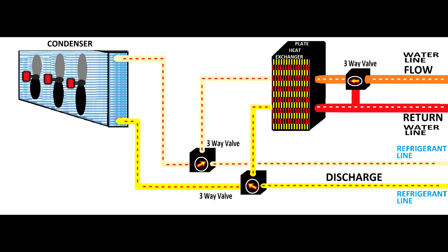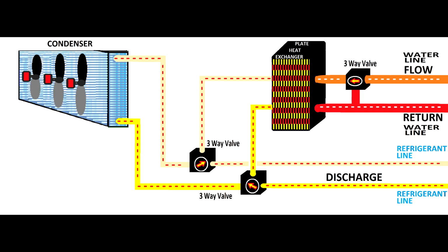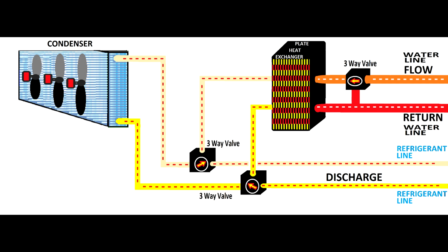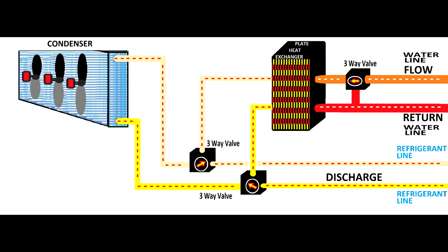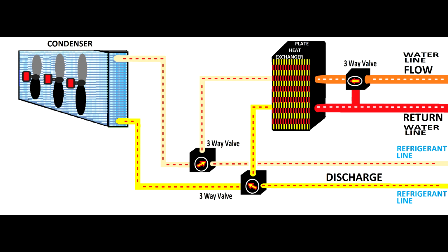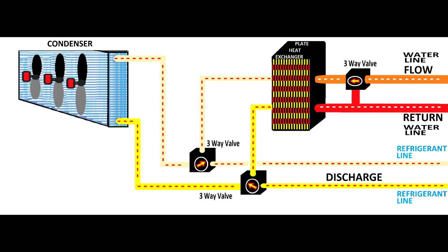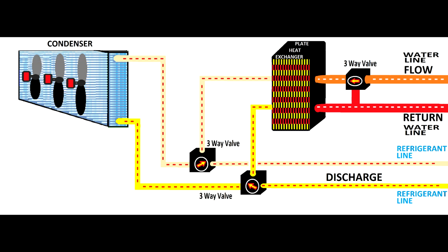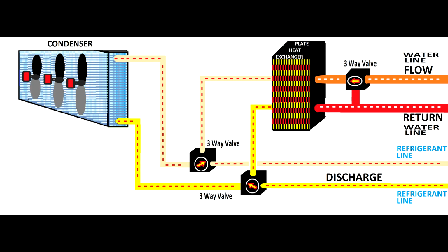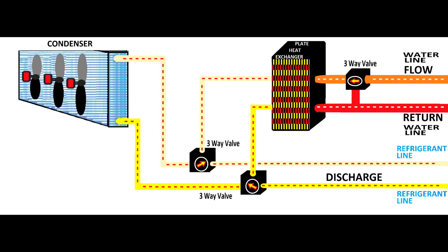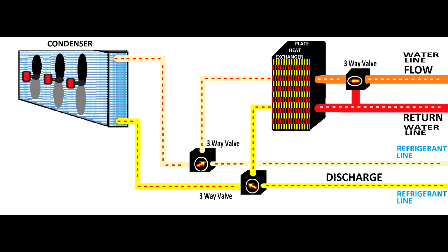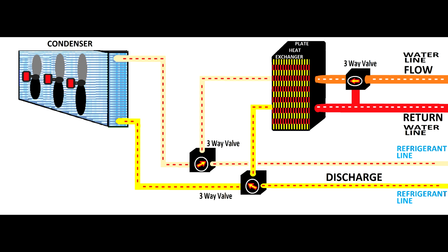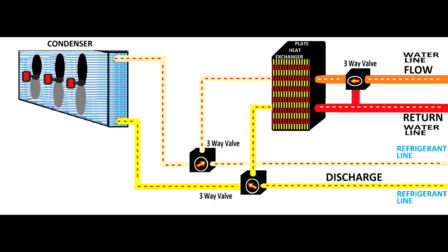If the pressure still grows in the system, then obviously the condenser fans start moving, and they will ramp up or down according to the quantity of air they have to move through the condenser to keep the refrigerant pressure under control. So you can see here, at the moment the condenser and the plate heat exchanger are sharing the refrigerant. We use the plate heat exchanger to cool the refrigerant, but at the same time I'm using the condenser to cool the refrigerant, because we need to control the temperature. So I still get the benefits of heating the water, but I also have to make sure that the refrigerant is kept within specific parameters, otherwise the HP can trip the system.